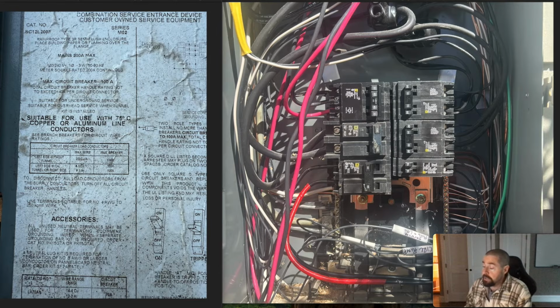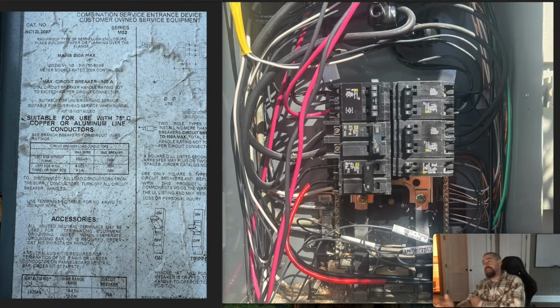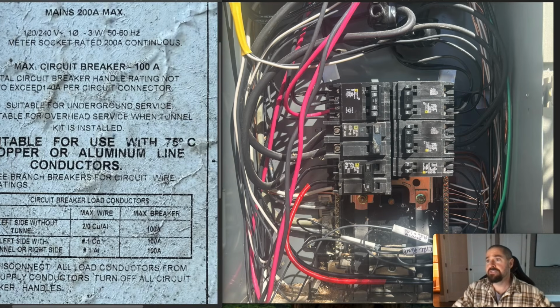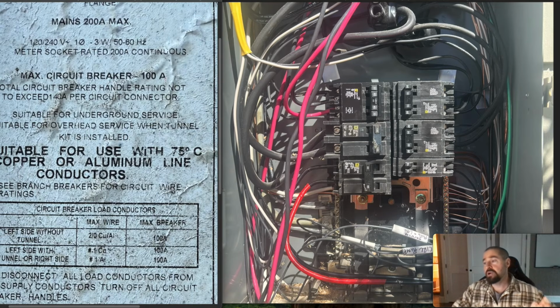and therefore it's a supply side connection. And per the National Electric Code, supply side connections, you can connect basically as much solar or battery as you want up into the rating of the service. So technically, you could connect up to 200 amps worth of solar and battery backfeed to this panel. But in this case, we are limited by the equipment here. You'll see over here on the left that every panel has a max circuit breaker, branch breaker rating. This one specifically has a max circuit breaker of 100 amps.